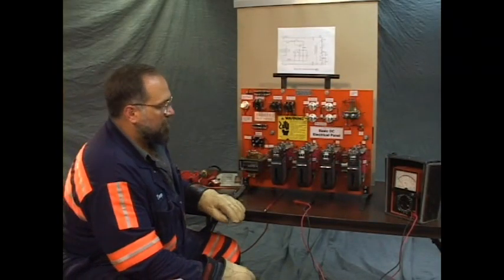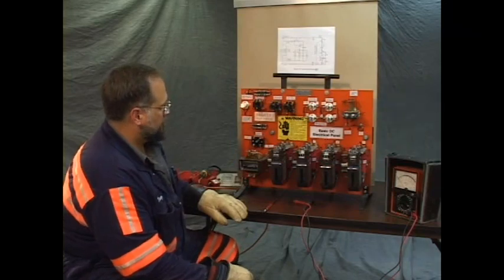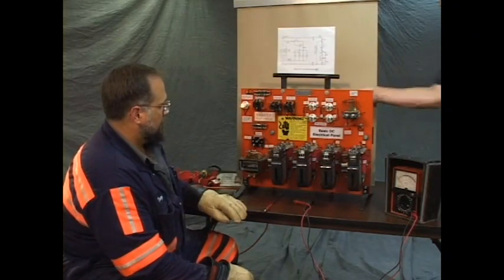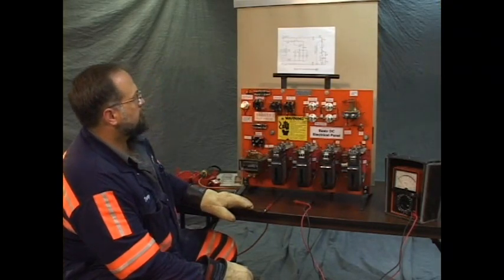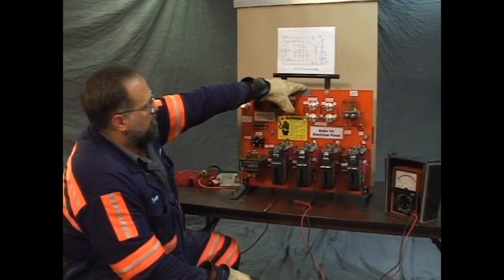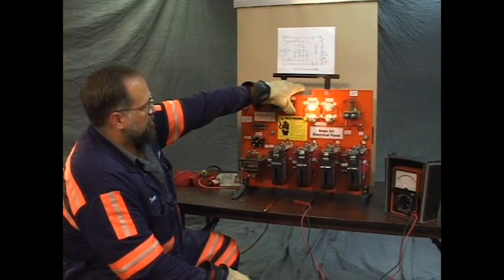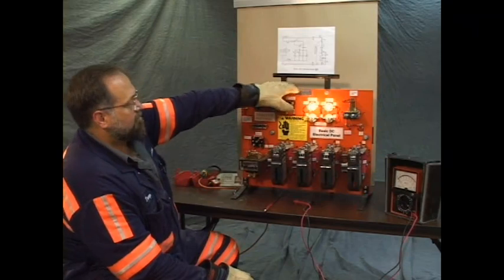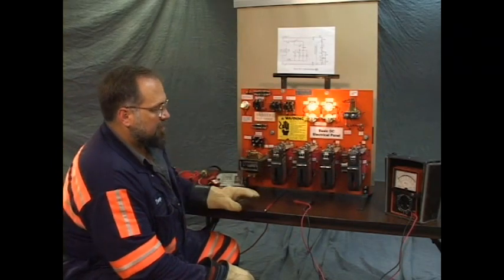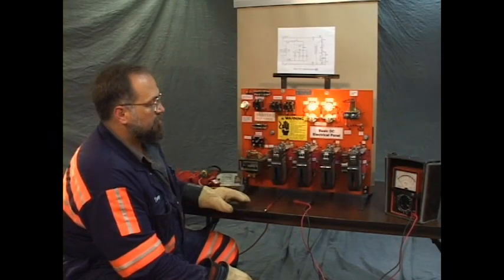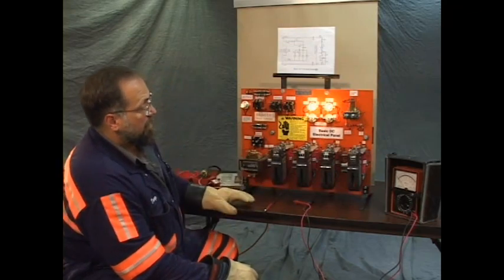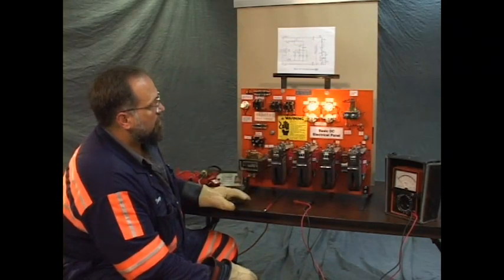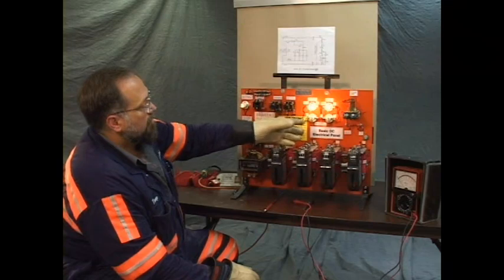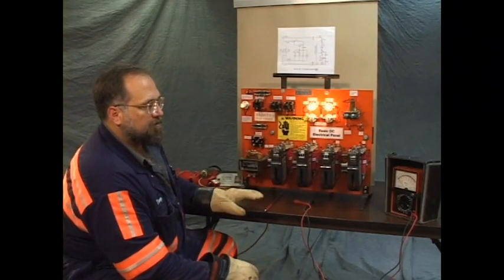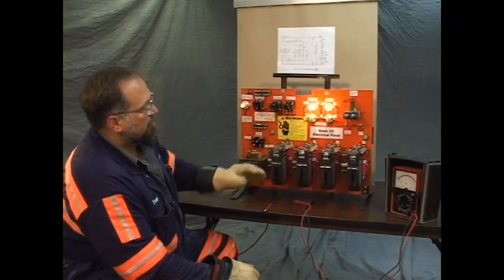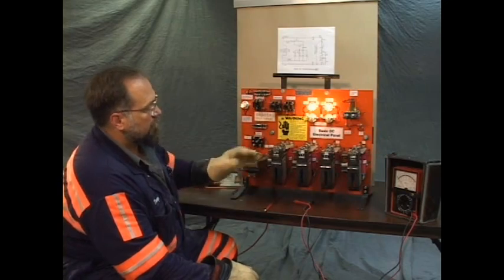Now with toggle switch number 7 thrown, we're going to install a problem. You press the start switch. We still had the 3 clicks. All of our contactors closed as they should. But the pattern of the lights is wrong. Now note, the lights indicate a motor action. Should we be controlling a motor with this starter instead of the lights?